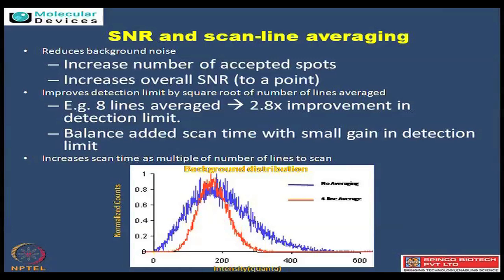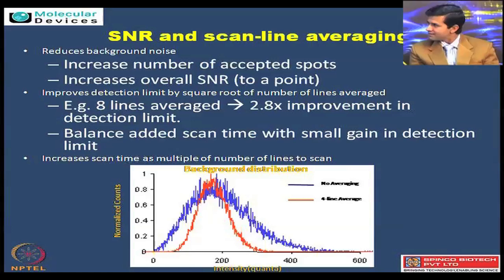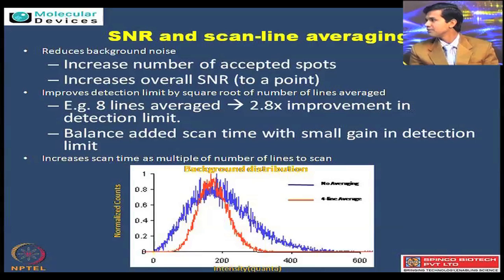Basically, if you scan once, an image is collected. If you want to have multiple scannings done so that all intensities can be averaged to get a signal value, it is seen that when you increase the number of scans - usually people prefer 2 to 3 - you then average them. This helps in reducing the noise so that you get a real good intensity coming up.